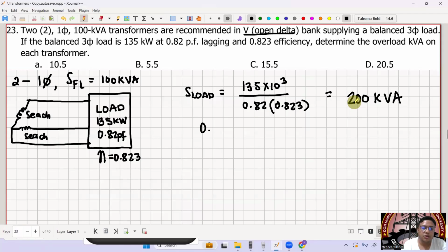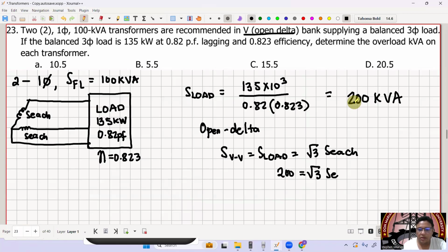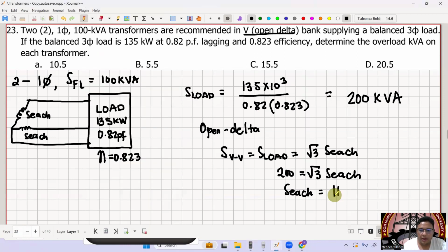Okay? So, therefore, SH now is equal to what? Okay? So, using your open delta formula, so yung ating S in open delta or S load is equal to square root of 3 ng SH. So that is now 200 is equal to square root of 3 times yung ating SH. So therefore, SH now is equal to what? So ilan yung magiging rating niya kapag kinonect natin siya sa open delta? So that is now 115.5 kVA.